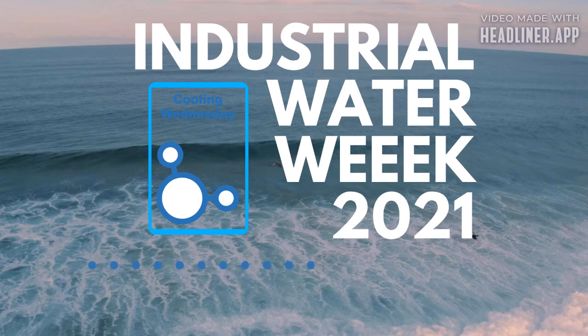Everybody's familiar with the open cooling tower setup, right? The large water volume connected usually to a plate and frame heat exchanger or a chiller. So we mentioned last week the closed circuit coolers and the evaporative condensers with the coils. So I just wanted to touch on a couple things to keep in mind when treating those units. Typically, those units, when they're outside, you'll see them with a spray pump right by the unit. And then it is connected to a piping that goes up the side of the unit. That's called a riser pipe. That's what transports the water out of the basin up to the top of the unit and then sprays it over the coil.